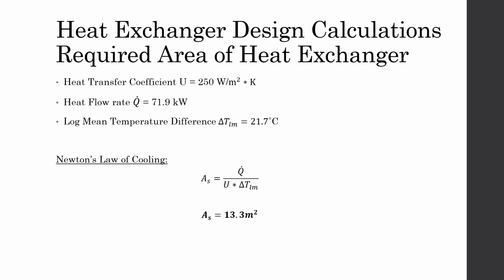Gas to liquid heat exchangers typically have a worse heat transfer coefficient when compared to liquid heat exchangers. Gas to liquid heat exchangers usually have heat transfer coefficients in the range of 250 watts per meter squared Kelvin. This will serve as a good estimate of the actual value of the heat transfer coefficient of the stack heat exchanger. For reference, a water-to-water heat exchanger typically has a heat transfer coefficient between 850 to 1,700 watts per meter squared Kelvin.